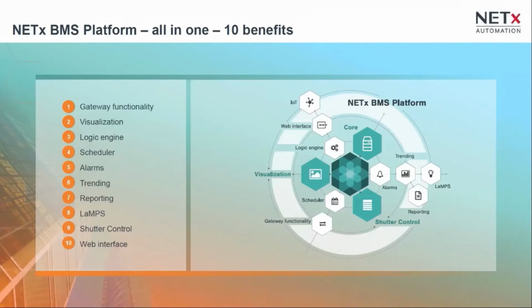In this slide, you see the general overview about our all-in-one solution, the BMS platform. The BMS platform, as mentioned, is a software running on a Windows platform, a Windows 10 PC for smaller projects, a Windows Server environment, Windows Server 2016 or Windows Server 2019 for larger projects. Anyway, you will have a gateway functionality, a bidirectional gateway to exchange data from KNX to a BACnet device, from a property management system to a HVAC system as well. Bidirectional exchange instead of having multiple different gateways for communication.